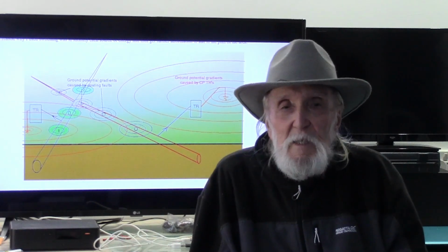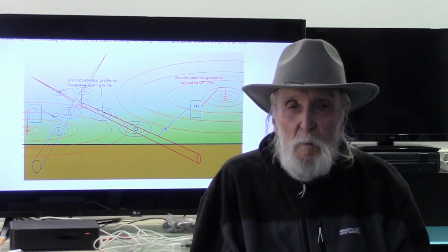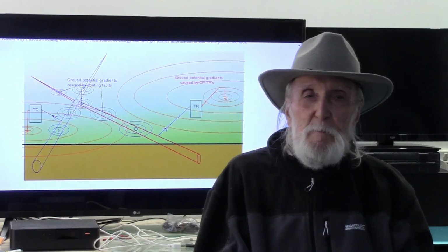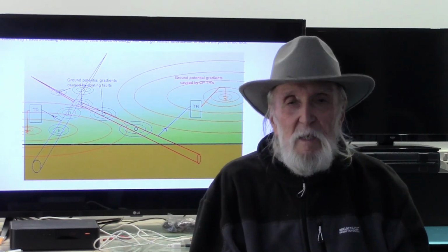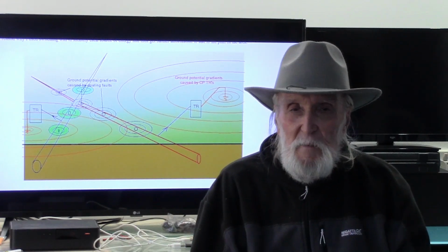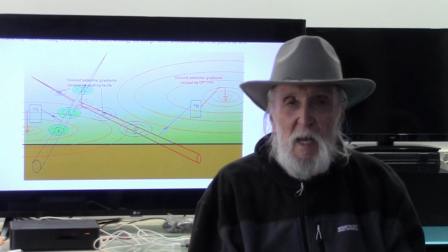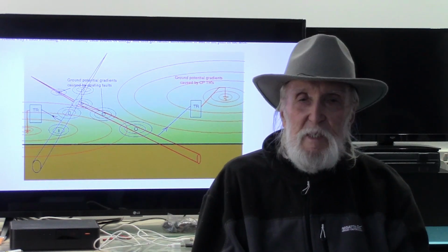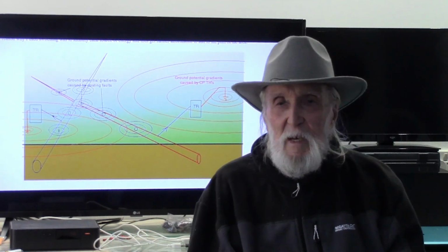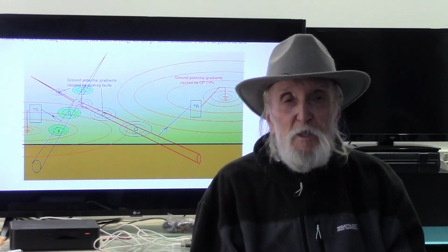It will allow us to reconcile voltage measurements which might otherwise be taken to indicate problems. It is sometimes advantageous to use recording voltmeters and oscilloscopes to examine the causes and likely effects of some of these ground surges.